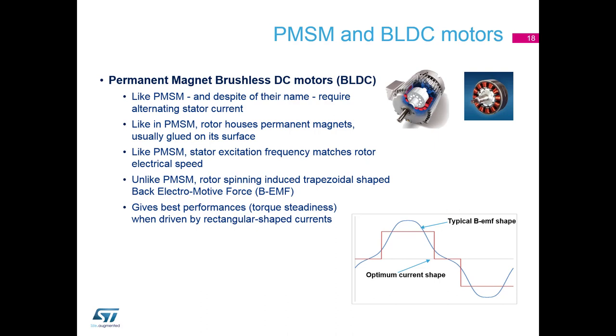The permanent magnet brushless motors, called in short BLDC, are like PMSM in many factors. They require alternating stator current. Like PMSM motors, the rotor houses permanent magnets, typically glued on the surface of the rotor. And like PMSM, their stator excitation frequency must be synchronous with the rotor mechanical speed. Unlike Permanent Magnet Synchronous motors, the rotor that spins within the stator inducts a trapezoid-shaped back electromotive force. And this motor gives the best performance when driven by rectangular shape currents.